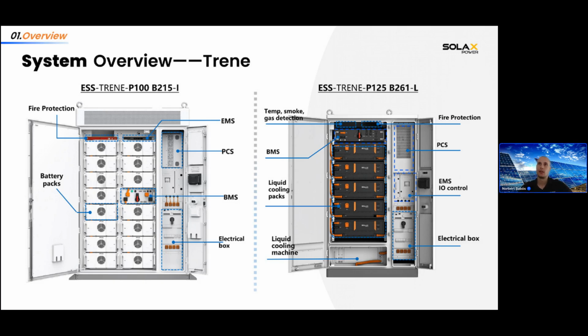For the TRENE, the AC coupled version, it's kind of similar, but there's a PCS instead of the inverter. Apart from that, the batteries are the same: fire protection also integrated, EMS on the top, BMS in the middle, electrical connections on the bottom right corner, and on the PCS the upper right corner. So this is for the air cooling version.